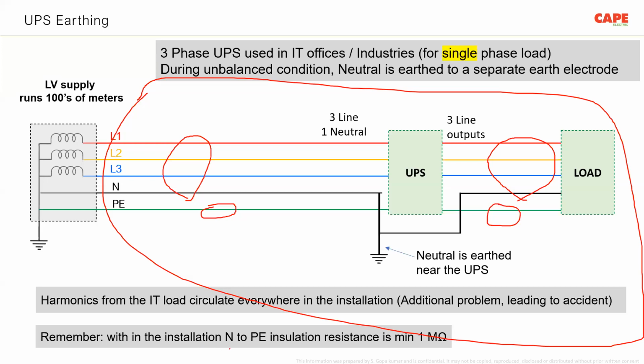The insulation resistance between any of the current carrying conductors and the earth conductor, PE, shall be minimum 1 megohm. This is a basic electrical safety requirement. If you want to know where this is written, you can refer to the IE Rules 1956. You can refer to the CEA Regulations 2010, I think Regulation number 33. Then you can refer to IS 732, you can refer to IS 3043. Everywhere this is written.